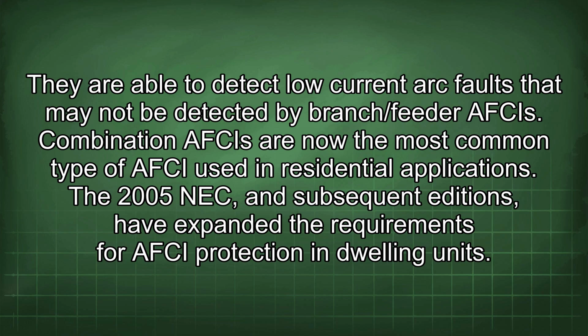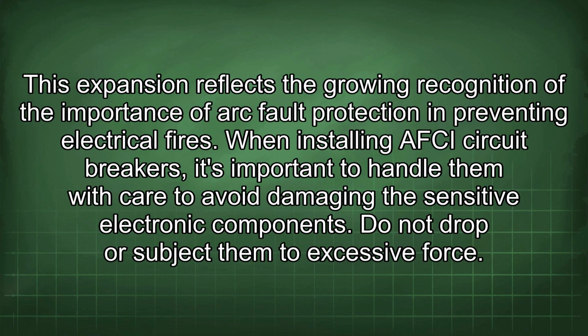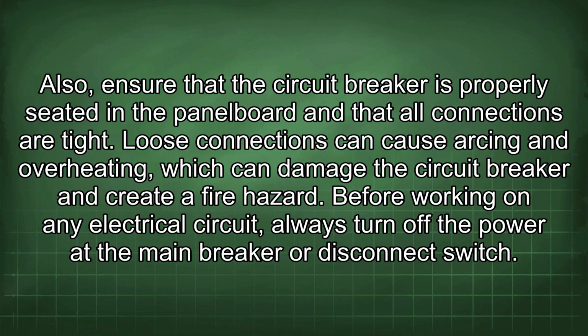The 2005 NEC and subsequent editions have expanded the requirements for AFCI protection in dwelling units. This expansion reflects the growing recognition of the importance of arc fault protection in preventing electrical fires. When installing AFCI circuit breakers, it's important to handle them with care to avoid damaging the sensitive electronic components. Do not drop or subject them to excessive force. Also, ensure that the circuit breaker is properly seated in the panel board and that all connections are tight. Loose connections can cause arcing and overheating, which can damage the circuit breaker and create a fire hazard.